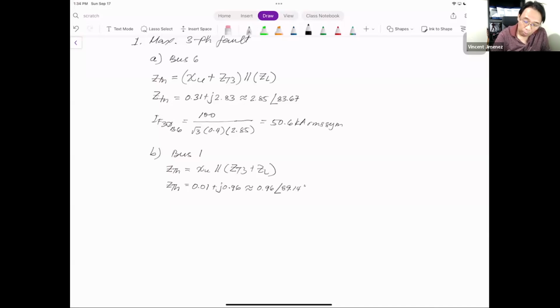Solving for the three-phase IF at bus 1, you would have the value 4.5 kA RMS symmetrical maximum. So the maximum three-phase fault is what we call the half cycle calculation.